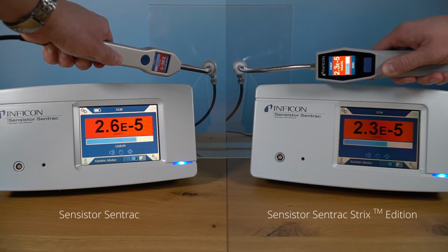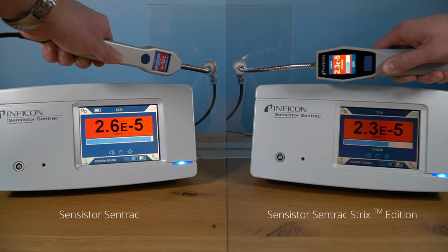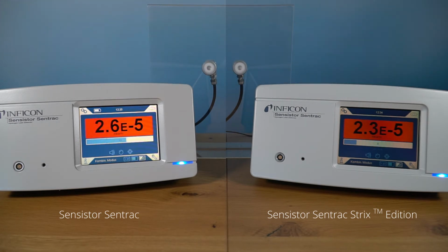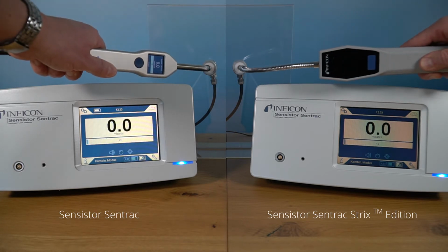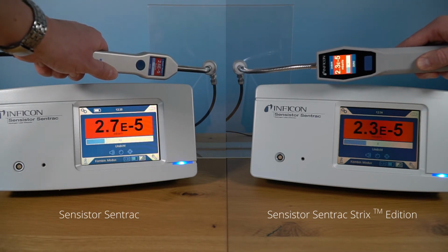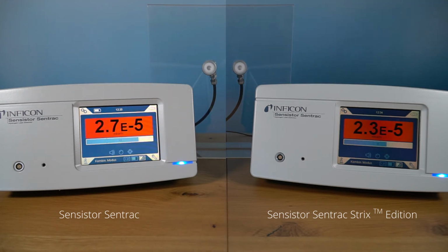By using the new Strix edition, you clearly reduce the risk to miss relevant leaks, as your test procedure is less dependent on the operator, on whether he is keeping the probe long enough on each spot, or whether he is testing slowly enough.